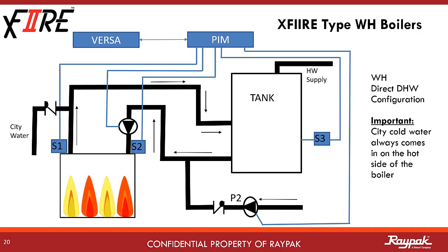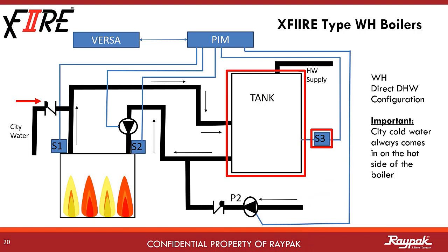Moving on from hydronic and into WH appliances, as in water heaters. When the X-Fire is purchased to be a water heater, there is only one mode of operation, so the plumbing is more specific. City cold water always comes in on the outlet side of the boiler to be mixed with the hot water the boiler is producing on the way to the tank. Here the tank works like a decoupler and the S3 sensor is placed in a dry well in the tank.